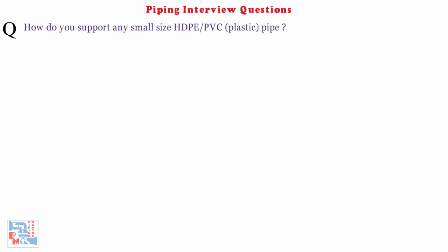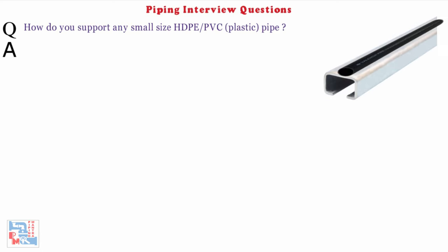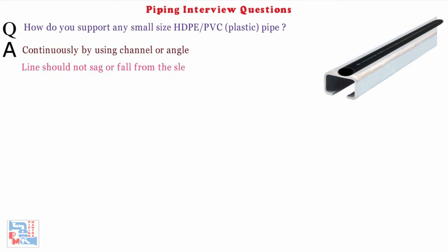Title block details, north direction, flow arrows. Next: how do you support any small size HDPE or PVC (plastic) pipe? It should be supported continuously by using channels or angles so that the line should not sag or fall from the sleeper or rack due to uneven expansion because of hot temperature.